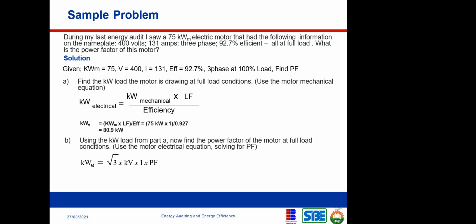Okay. So secondly, now we know what the kilowatt electrical is. We know that the formula for kilowatt electrical is equal to the root 3 times kilovolts times current times power factor. Now we don't know the power factor. That's what we are told to find. We know what the current is, we know what the kilovolt is, and we know what the kilowatt electrical is. So we now put in this 80.9 for kilowatt electrical.